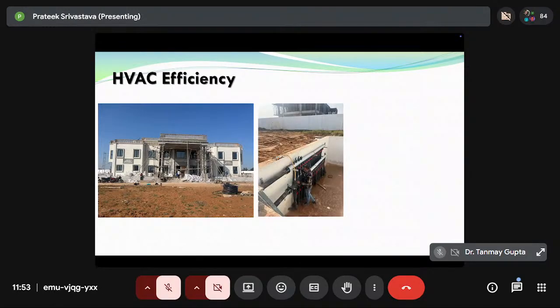So what happened is we have done 20 bores in the vicinity of the project. In the normal air conditioning system, we just cool the building and we dump the heat outside. Here, we are putting the heat from the building into the ground. So we have 20 bores, each 100 meters deep, and if you see these black pipes coming here, this is a manifold which we have created.